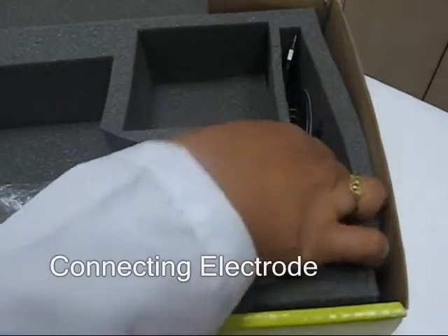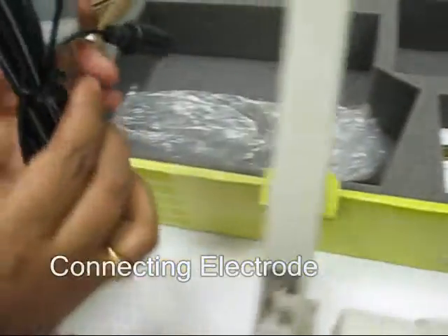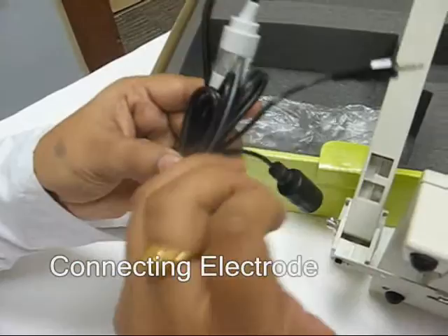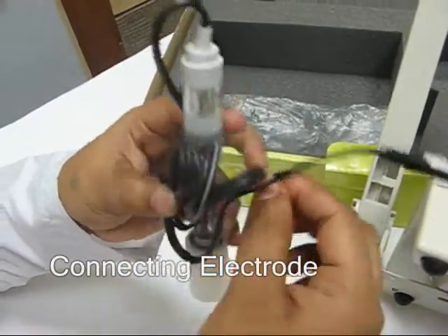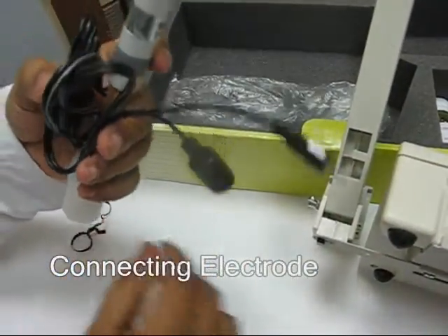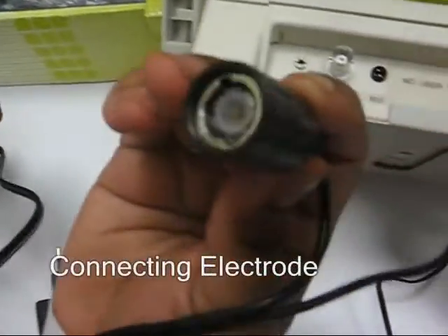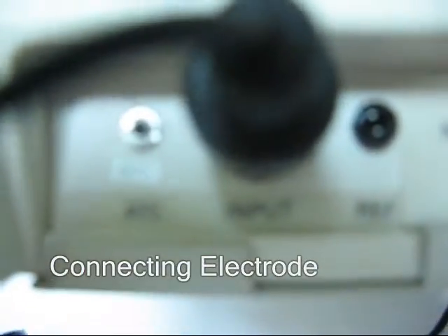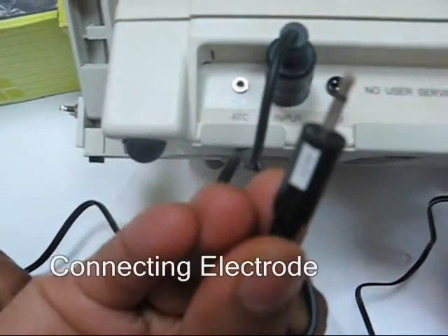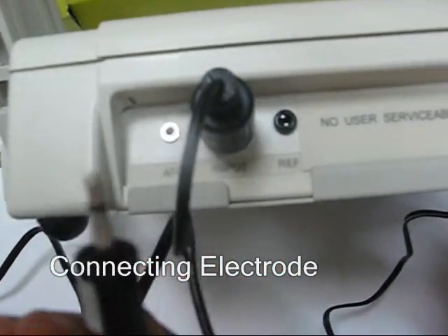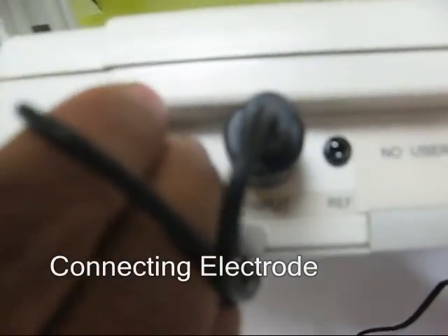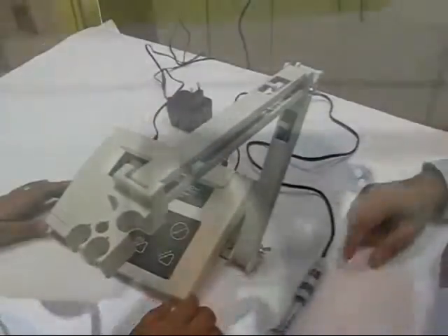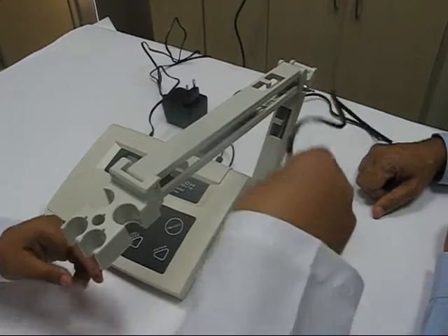Let's get the electrode out now. Unwrap it. The BNC connector goes on to the socket marked input. Simple to use. Plug it. Now you have the 2.5 mm phono connector, which is the ATC element, which plugs in to the ATC socket. Let's fix the electrode onto the stand and dress the cable.